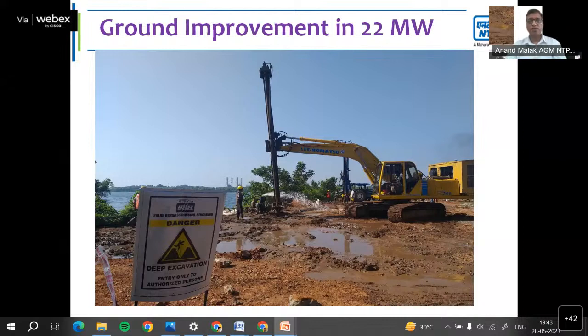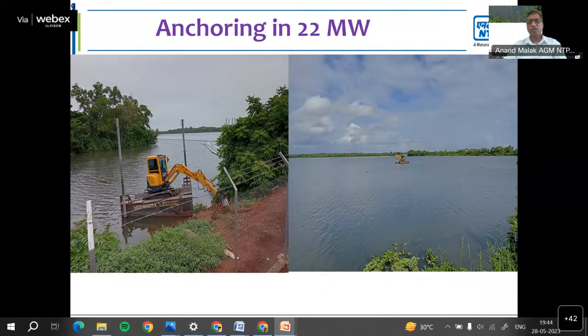Whereas in the case of the 70 megawatt, we don't have any access to land. The inverters, inverter transformers, HT panel and SCADA panel are entirely in the water, on the floating platform. These are photographs of the anchoring. It is well known that these floating pontoons carry small equipment by which we do this anchoring.